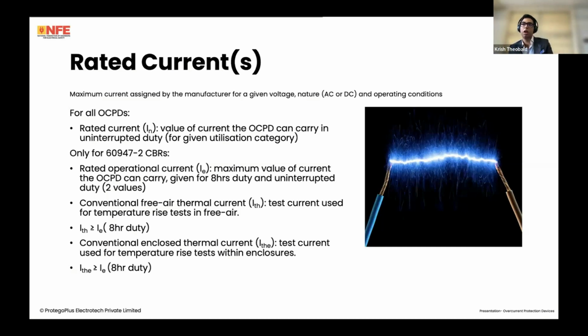Then there is also the conventional enclosed thermal current, which is a test current used for OCPDs inside enclosures. So, for instance, a switch fuse disconnector would very commonly be inside an enclosure, and so would an MCCB when it is operated through the rotary handle. Usually these are given. So for MCCBs, you will get these values because MCCBs also correspond to 60947 Part 2. Once again, these values have to be greater than or equal to the 8-hour duty value for the rated operational current, because if a circuit breaker is intended to be installed inside an enclosure, you would obviously want it to be able to run at that particular load current for longer than its rated duty cycle. Again, if the device is meant for 24-hour duty, then it's a different story. Again, it would probably be rated for that.